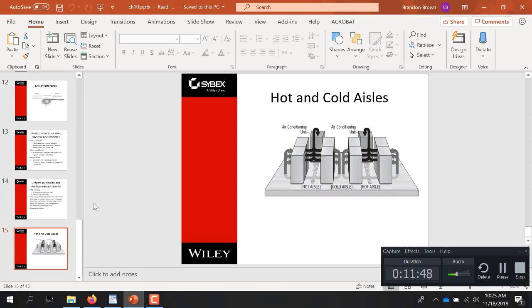They have a good example of it here on slide 15: cold air comes from the floor, goes through the rack, and there's a heat exchange, then it goes up to the air conditioning unit and is turned back into cold air, condensed and everything else.